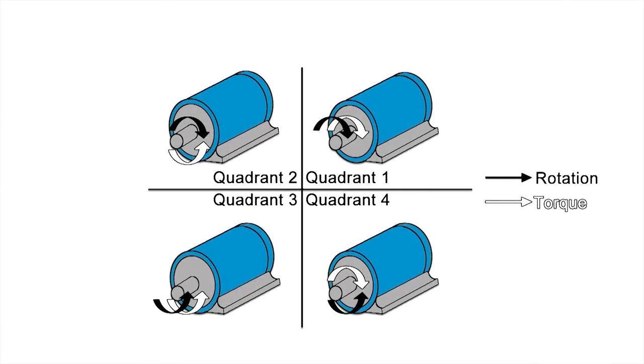A regenerative drive is essentially two coordinated DC drives integrated within shared housing. One drive operates Quadrants 1 and 4, and the other operates Quadrants 2 and 3. Sophisticated electronic control circuits then provide interlocking between the two opposing drive sections for reliable control of the direction of the motor's torque and the direction of the motor's rotation.